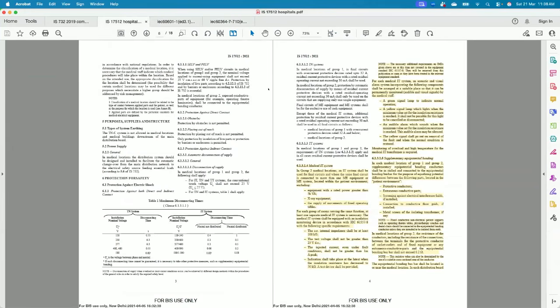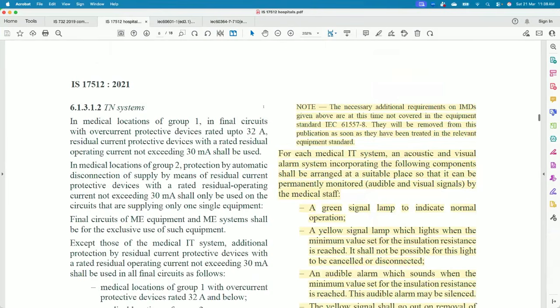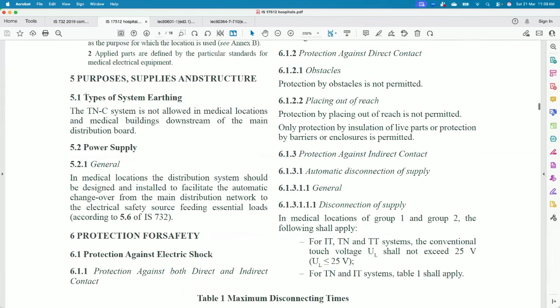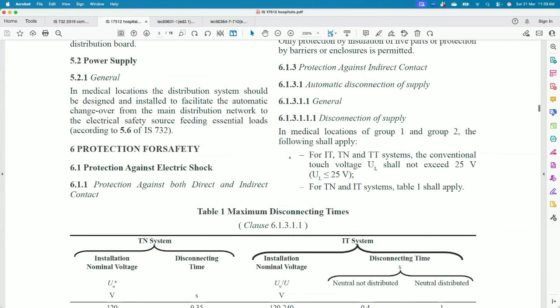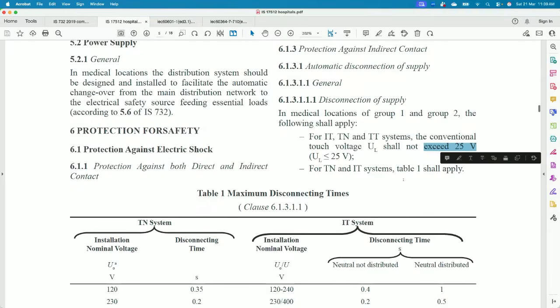Now, if you go here, let me read a little bit for your information. Supply, type of earthing system. TNC system is not allowed. That means you can go for the other types of systems. For IT, I'm talking about clause 6.1.3.1.1, disconnection of supply. Disconnection of supply means during a fault, the electricity has to be disconnected within a certain time. In medical location, group 1 and group 2, the following shall apply. In TN, TT and IT systems, conventional touch voltage not exceeding 25 volt. That means during a fault, the touch voltage has to be limited to less than 25 volt.